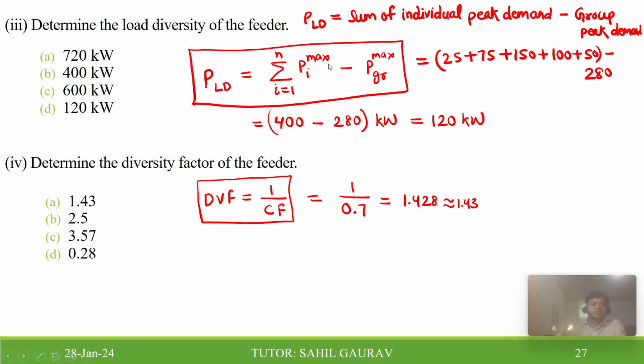So for load diversity, you have to just remember the expression: load diversity is the sum of individual peak demands minus the group peak demand. So it is 120 kilowatt. Now you have to find the diversity factor of the feeder. The diversity factor is the reciprocal of the coincidence factor. So it is 1 divided by 0.7, which comes to 1.43. So 120 kilowatt is the correct option for the third part, and for the last part it is 1.43.